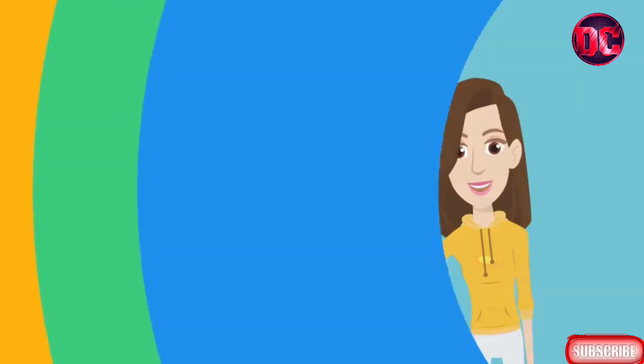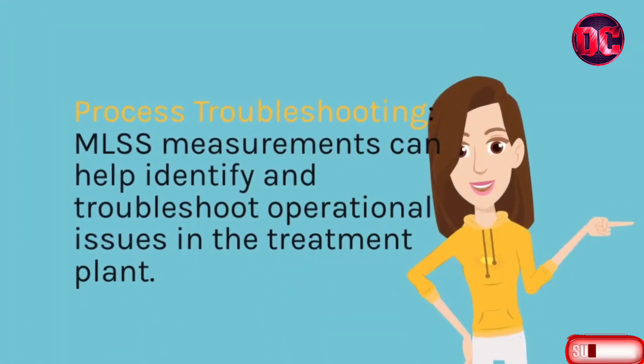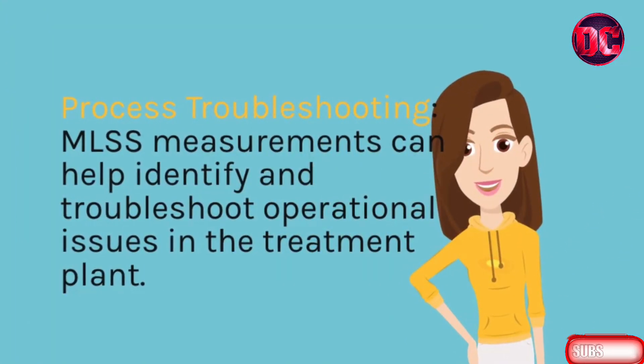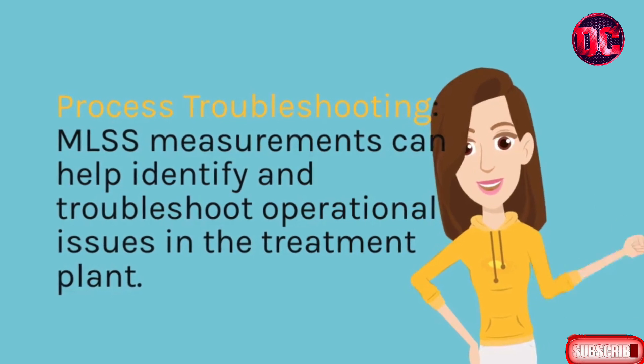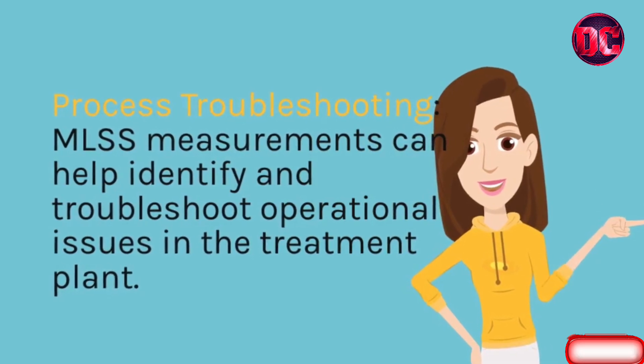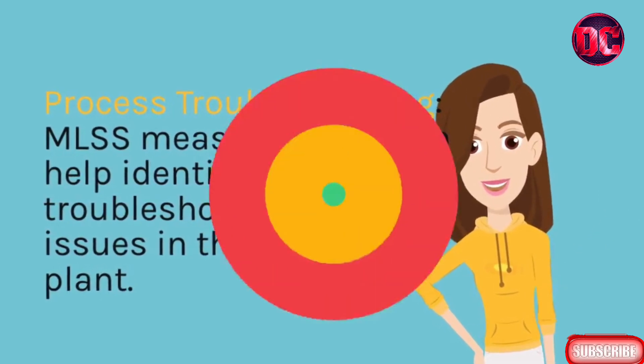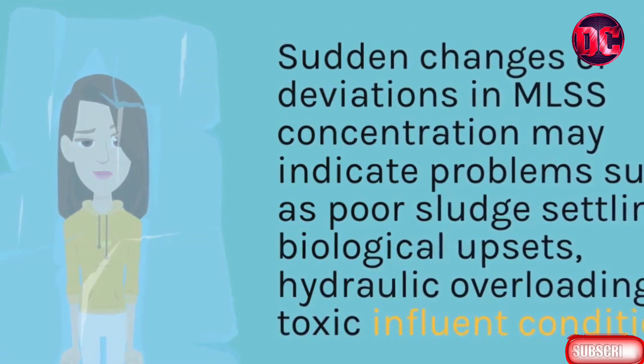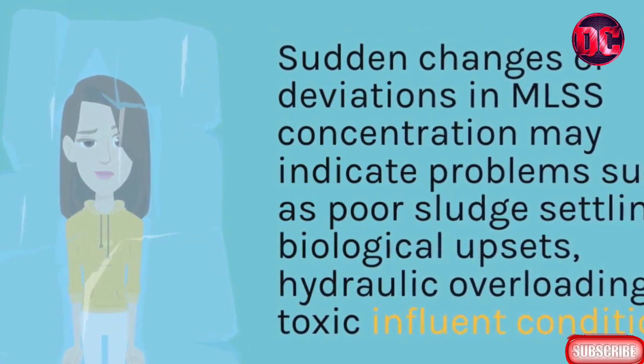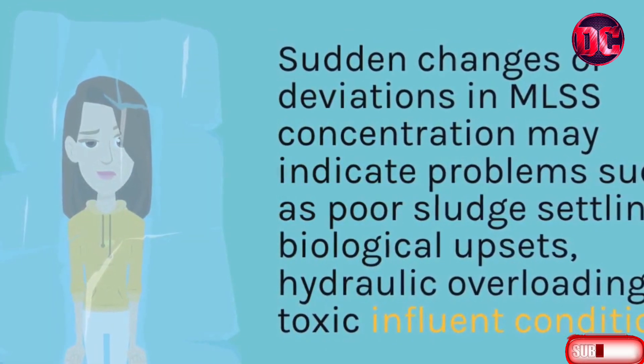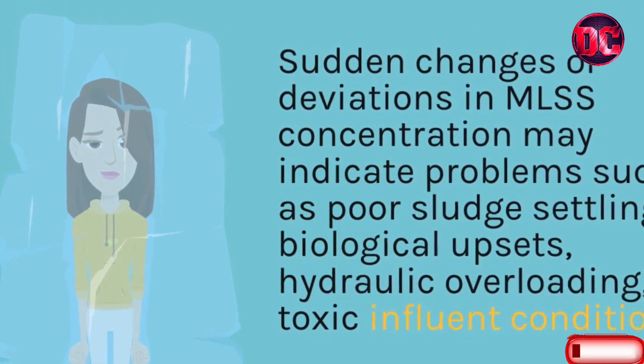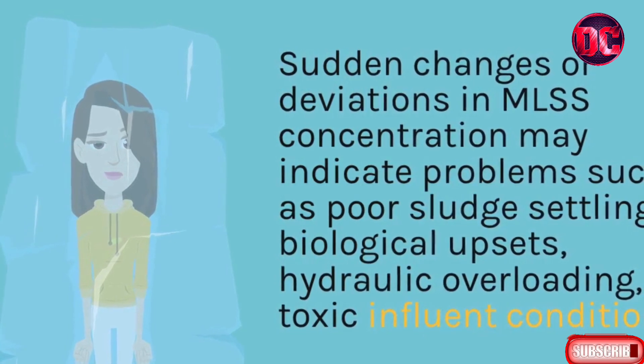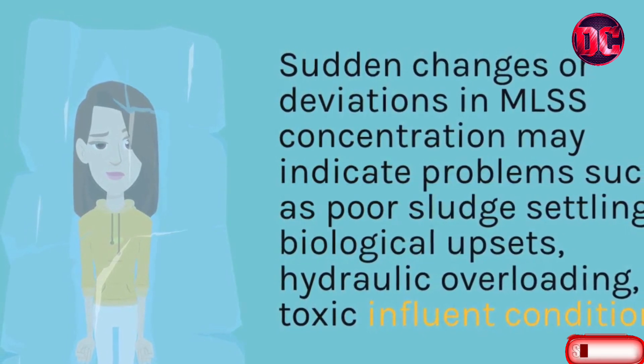MLSS measurements can help identify and troubleshoot operational issues in the treatment plant. Sudden changes or deviations in MLSS concentration may indicate problems such as poor sludge settling, biological upsets, hydraulic overloading, or toxic influent conditions.